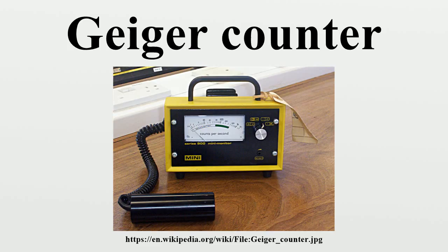However, to facilitate more localized measurements such as surface dose, the position of the tube in the enclosure is sometimes indicated by targets on the enclosure, so an accurate measurement can be made with the tube at the correct orientation and a known distance from the surface.